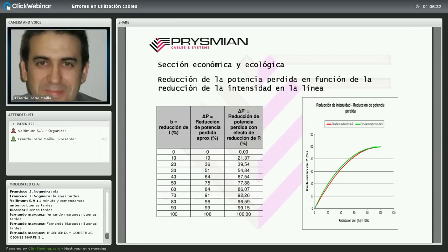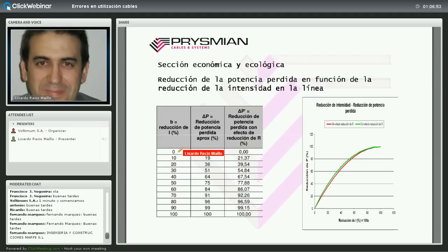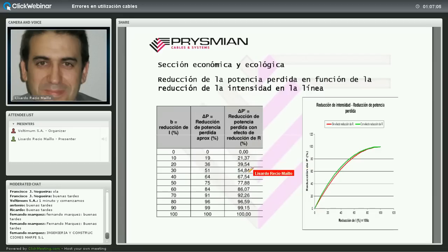Podemos aumentar la sección respecto al mínimo técnico y calcular ahorros a lo largo de la vida útil del cable. Si reducimos la intensidad máxima un 10%, las pérdidas se reducen un 21%; un 20% supone un 40% de ahorro; un 30% supone un 55% de ahorro. No hay linealidad porque las pérdidas son proporcionales al cuadrado de la intensidad. Reducir un poco la intensidad máxima puede amortizar uno, dos o incluso tres saltos de sección en muy poco tiempo.